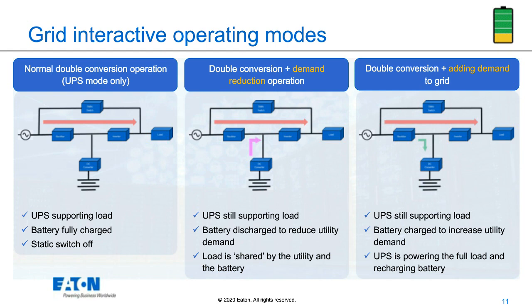The static switch and bypass circuitry is only needed if the UPS becomes overloaded or suffers a failure. So in these modes, the UPS is supporting the IT equipment load just like we always expected, and the battery is fully charged.